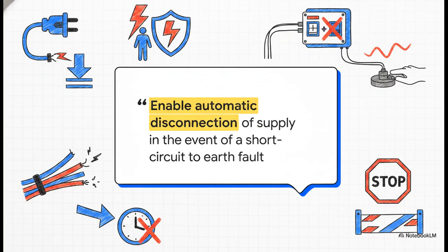I want you to listen closely to these words. Enable automatic disconnection of supply in the event of a short circuit to earth fault or excessive earth leakage current through protective earthing arrangements. That is the golden rule, right there. The entire goal of Section 5 is saving lives and property by preventing dangerous touch voltages. When things go sideways, the system absolutely must recognize the fault and cut the power instantly, before anyone even has a chance to get hurt.